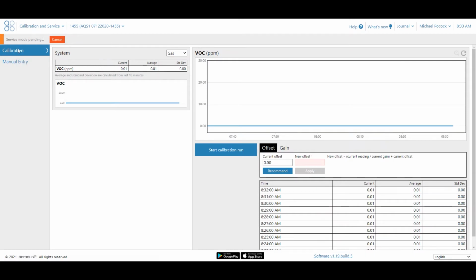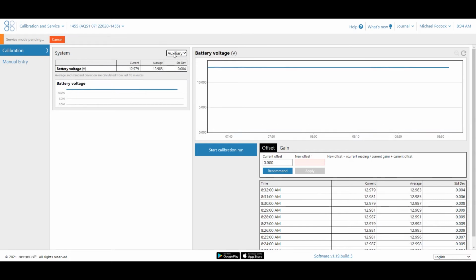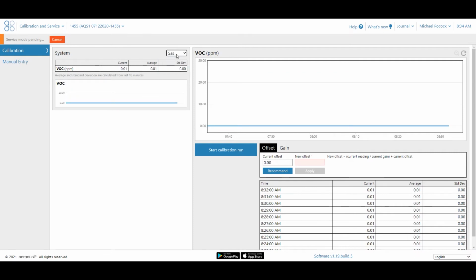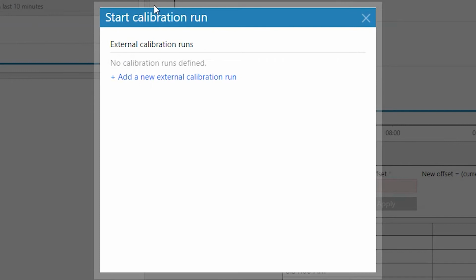Okay, I'm going to go to the next step. What you're seeing in this box here is the current reading for the system. There are different modules here. You can have your particles, your weather station or battery voltage, and your gas. We want to be on gas, so obviously we're doing the VOC module. That's a gas. The VOC reading at the moment is 0.01. I have the zero air connected to this monitor, so you can just click Start Calibration Run, then we can get going here. What we want to do is start a new calibration run by adding this.